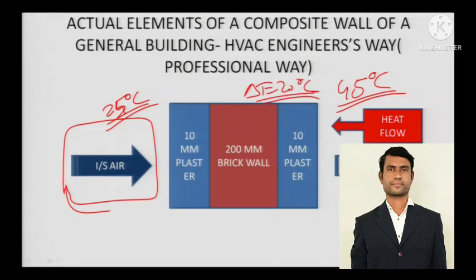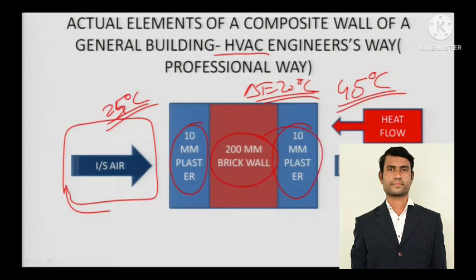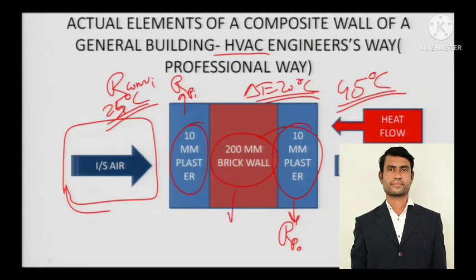That is a huge Delta T, and this heat has to be overcome and removed — that is what HVAC engineers in consultancies do. It's a brick wall, plaster inside, plaster outside. As we have seen in theory, each and every element of the wall offers resistance — air also offers resistance. So there is convection resistance inside, convection resistance outside, resistance for inside plaster, outside plaster, and the brick wall.